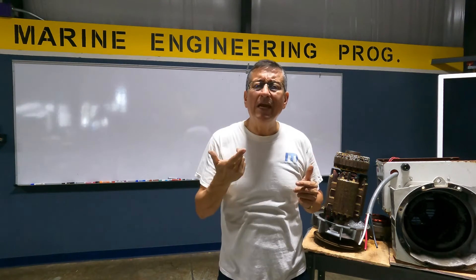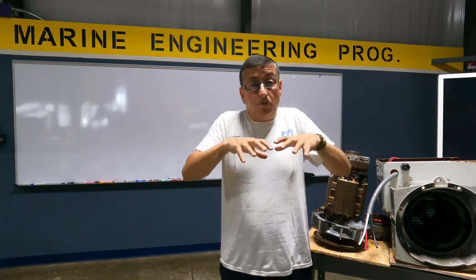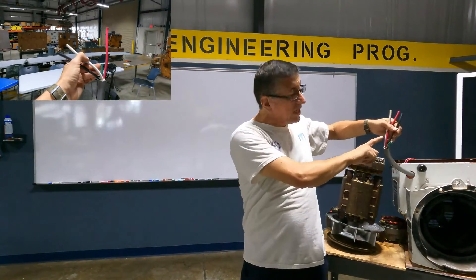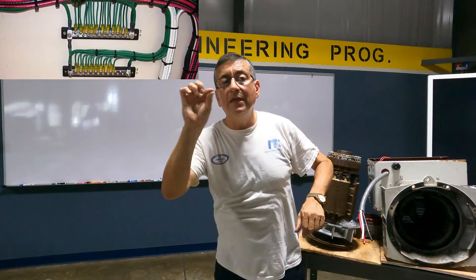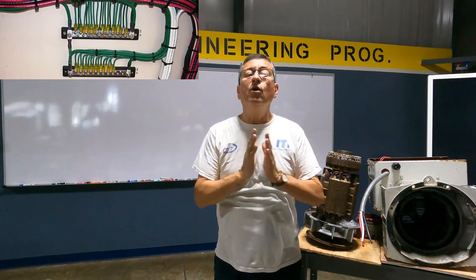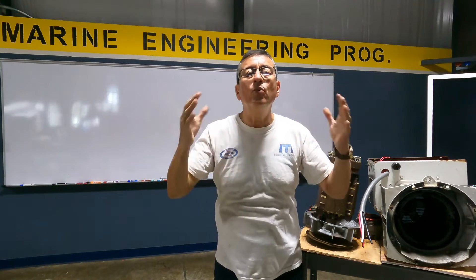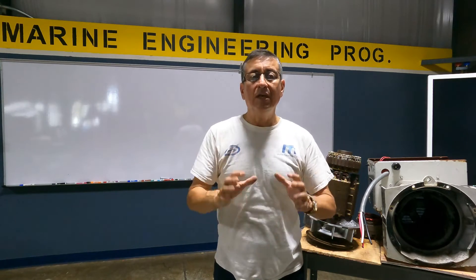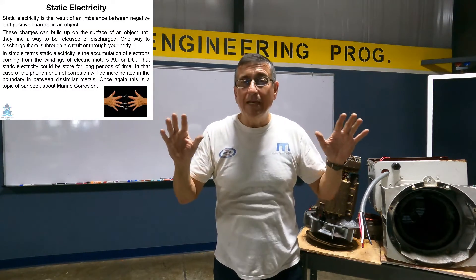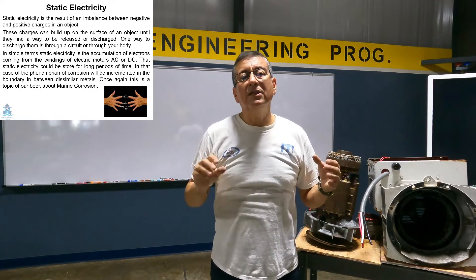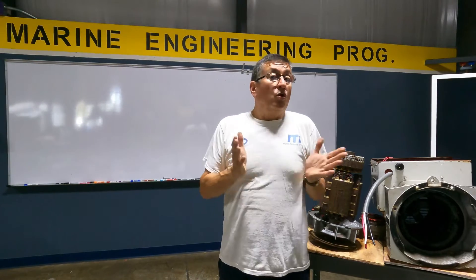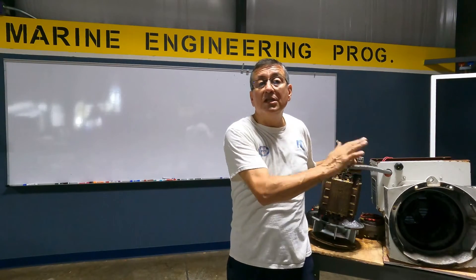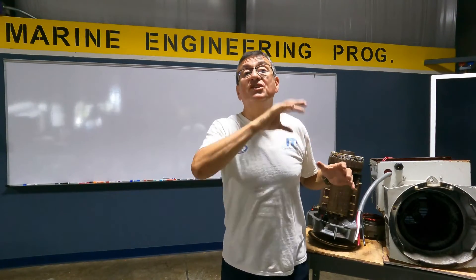What is the function of the ground — the green cable? The green cable is coming from the housing. At that point, it's connected to the housing of the generator, and that green cable enters and feeds the ground bus bar. What is the function of that ground cable? It drains current. The current that is stored in the case of the motor, in the case of the refrigerator, in the case of the equipment — some current, normally static electricity — is stored there and that current is drained through that ground. Or, in some cases, if the hot line is touching the housing of the equipment, it drains that charge to ground.